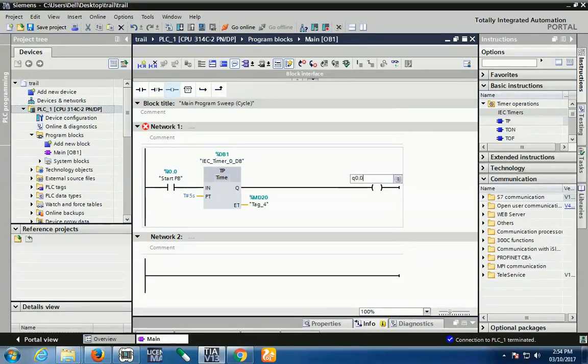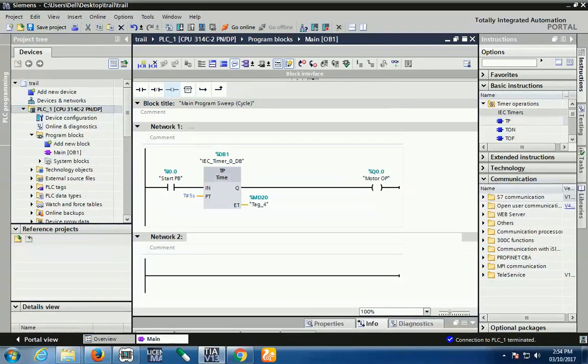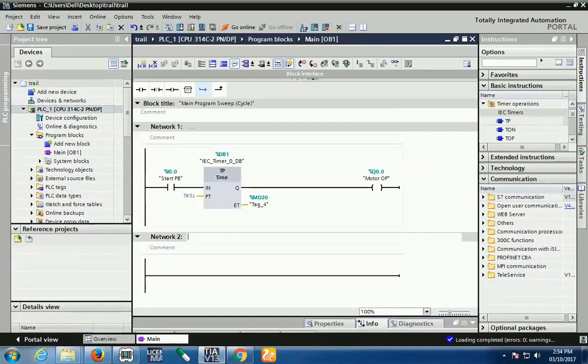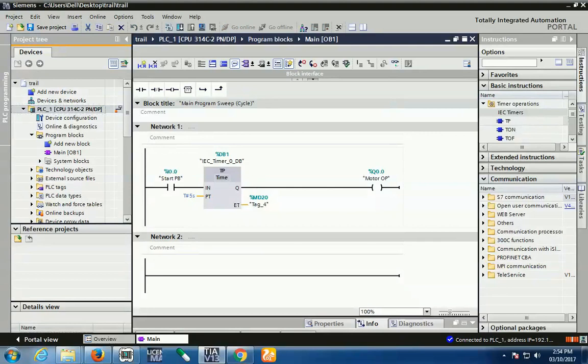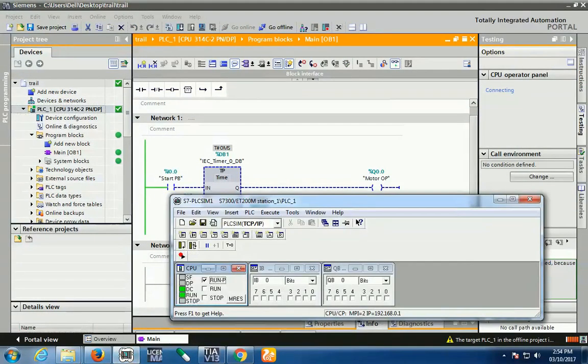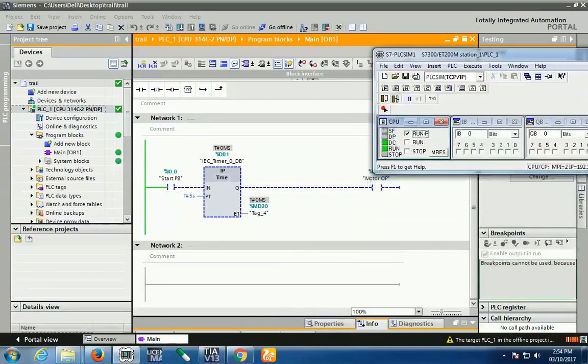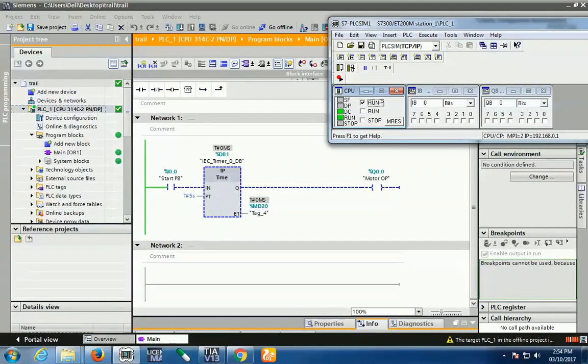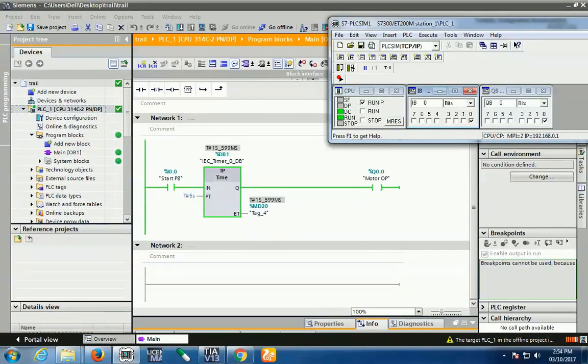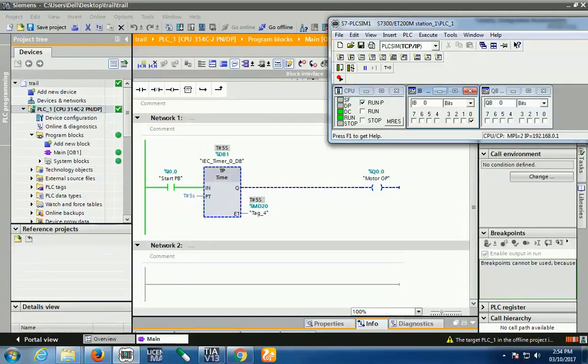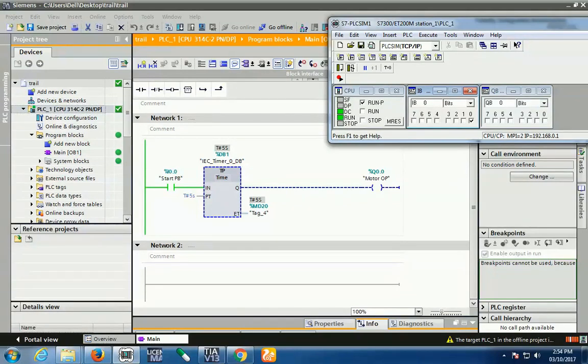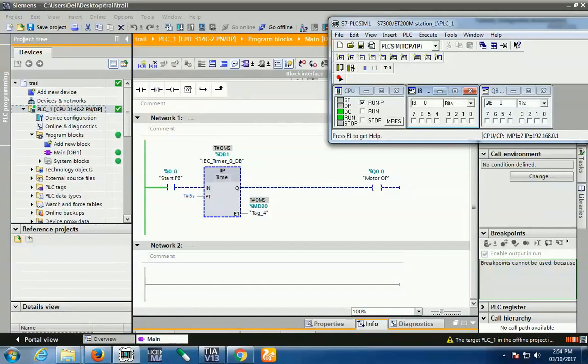Now your timer configuration is completed. I'll download and monitor online. Let's check if it's working or not. You can see here this is my input. If I press, you see the time is running, my output is on. After 5 seconds, output is off. You can see the enable command is still high, the signal is high, but it does not start again because it works only on positive edge detection.